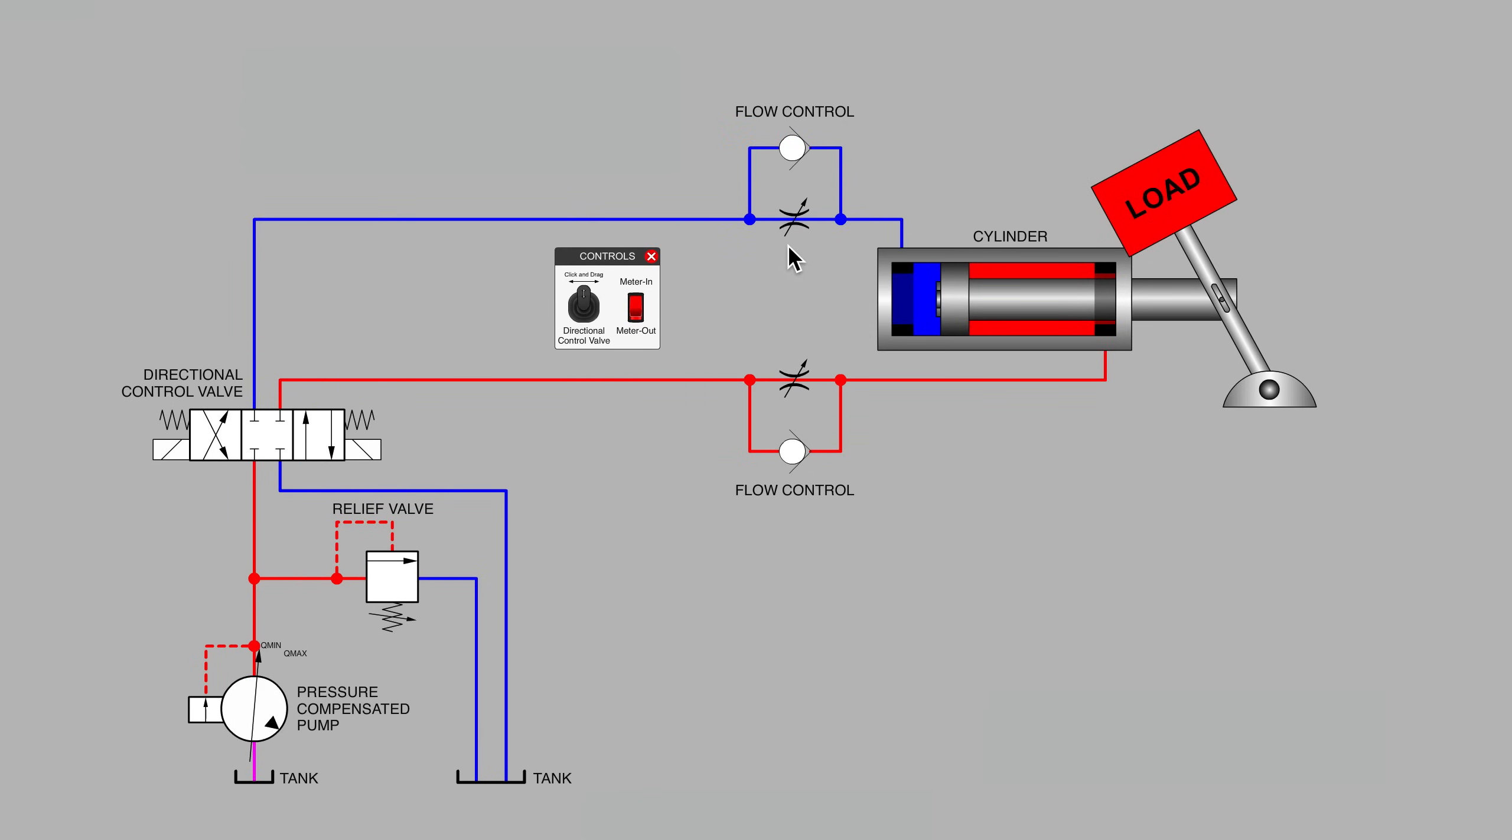At its most basic level, a flow control as used for controlling the speed of a hydraulic cylinder is often nothing more than a variable orifice in the form of a needle valve along with a return flow check valve. And the return flow check valve is usually built right into the same package as the needle valve.